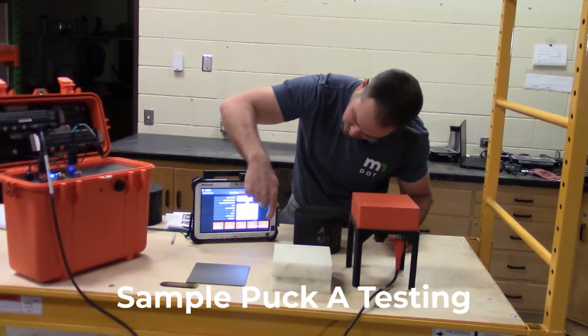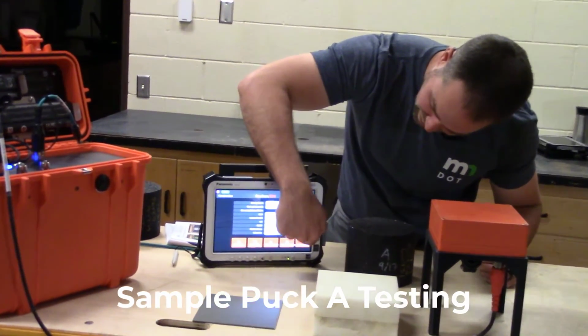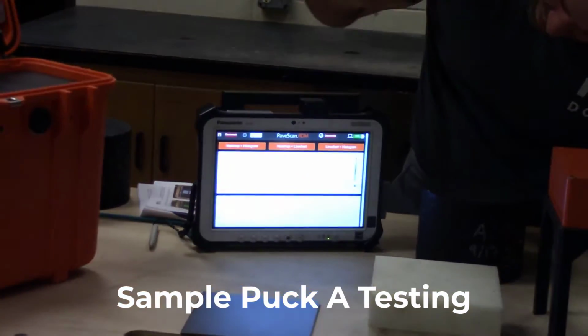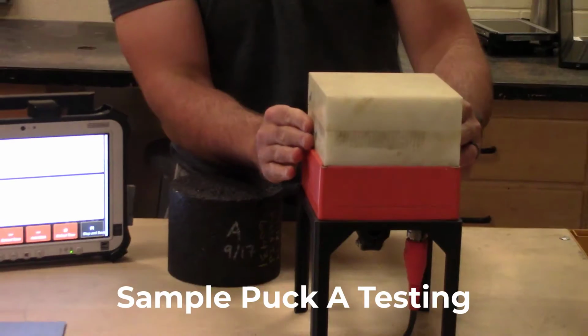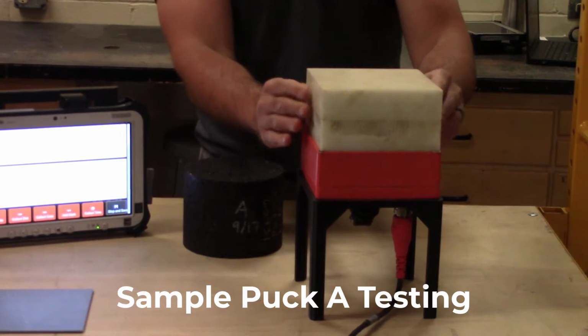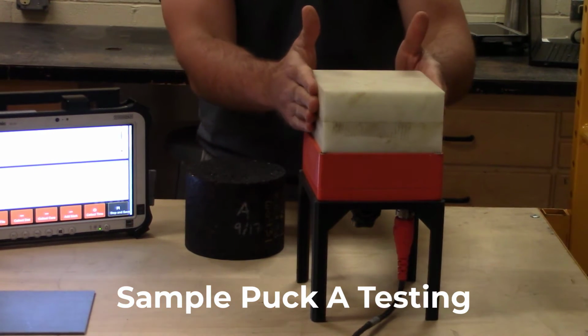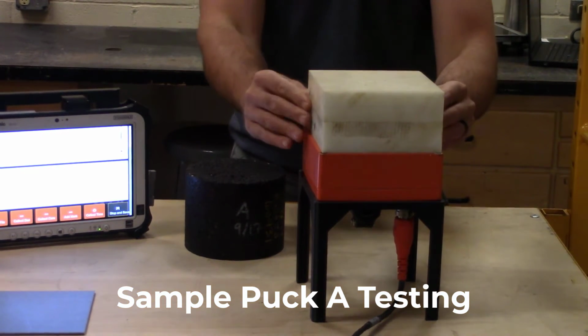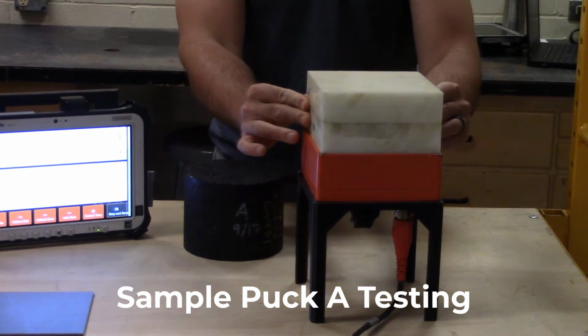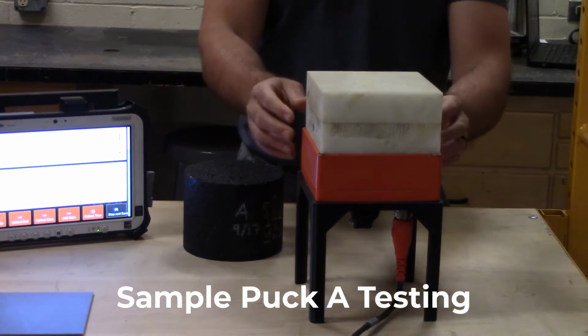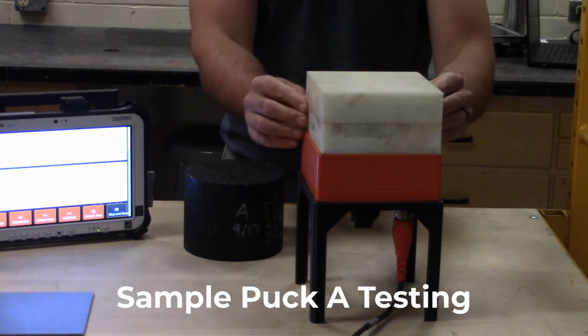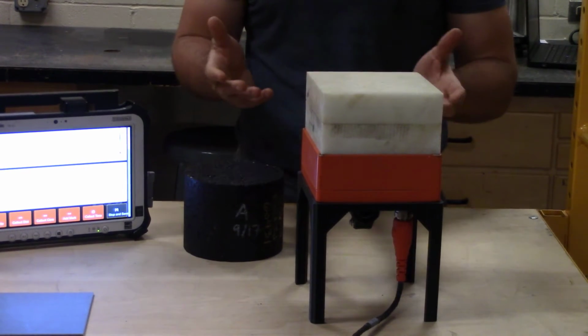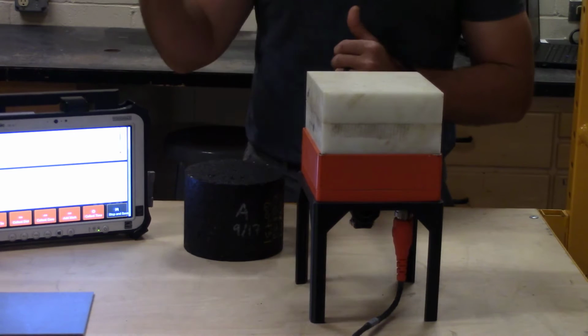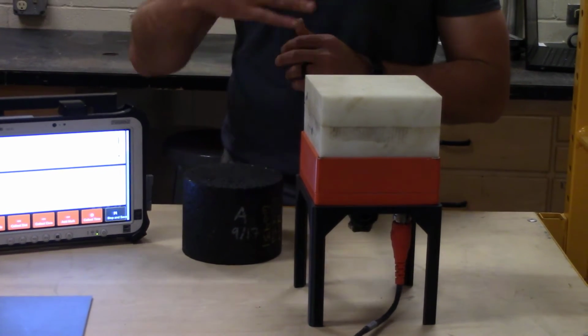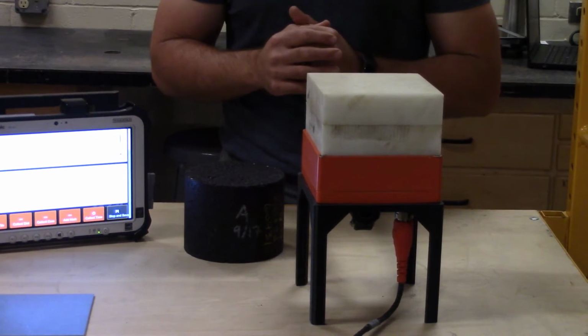So to collect data, we're just simply going to press collect data, and that's going to get us into our data collection screen here. It's going to be a series of 4 15-second measurements, and the first one will be simply with the 2 Delrin blocks placed on top of the sensor. This is equivalent to our air testing from the field, where we're using this to eliminate some of the background noise. And once I press collect time, it's going to be collecting continuously for 60 seconds.